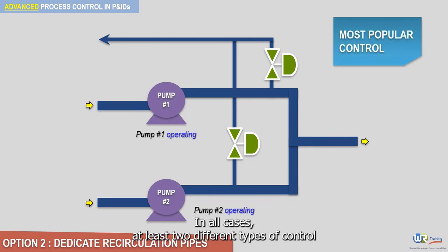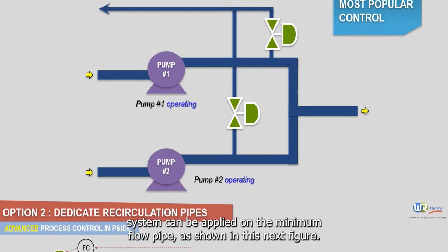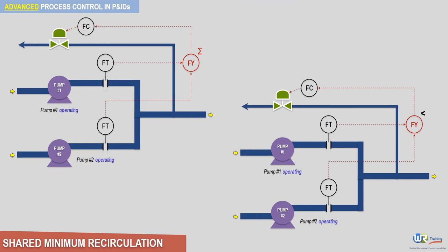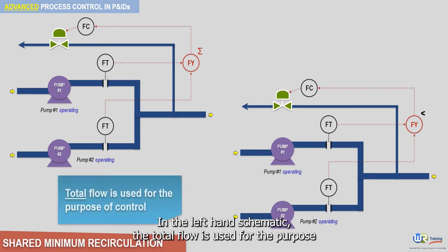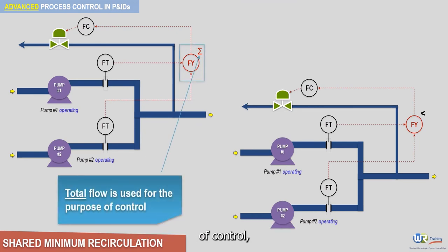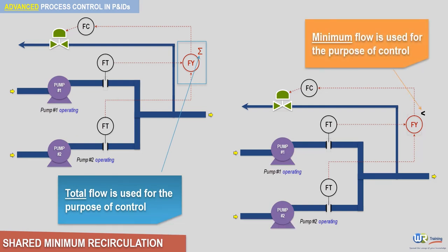In all cases, at least two different types of control system can be applied on the minimum flow pipe, as shown in this next figure. In the left-hand schematic, the total flow is used for the purpose of control, while in the right-hand schematic, the minimum flow is used.